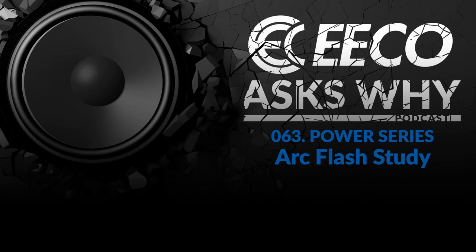What type of information do we need to even get started with the arc flash study? There's a lot that goes into it. It would be a good point to discuss what an arc is briefly. There are a couple different kinds of faults. A bolted fault is where, for example, a contractor terminated A phase on B phase on a breaker — that creates a bolted fault, the breaker trips, and everything clears the fault. Or maybe someone inadvertently ran a bolt between a piece of bus bar and ground — again, that would be considered a bolted fault, and it would be pretty easily detected through testing and then fixed.